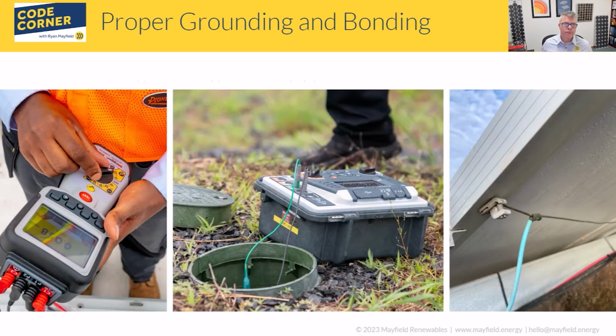And so here we see a couple of pictures. That first one on the left is a digital low resistance ohm meter. We'll show you some more about that in a few minutes. So a digital low resistance ohm meter, in short, is able to inject a small amount of current into the system under test, and it's able to measure and calculate resistance based on what the actual conditions are. And so this is a great handheld tester to use when you are trying to verify bonding or continuity of electrical equipment that is spaced apart.